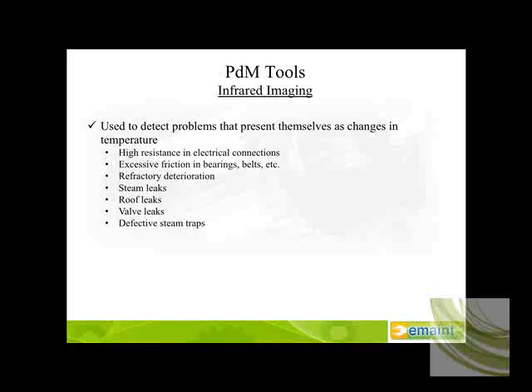But typically we're looking at high resistance in electrical connections, excessive friction, which certainly we know under lubrication, over lubrication in bearings creates that. So you have the capability of seeing in the bearing housings external heat that can be seen with an infrared camera. Refractory deterioration in boilers, for instance, steam leaks, roof leaks, valve leaks, insulation voids if we're looking at the interior or exterior of our facilities. It's a very versatile tool.